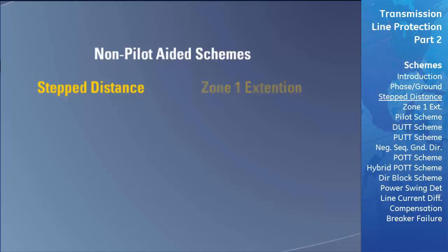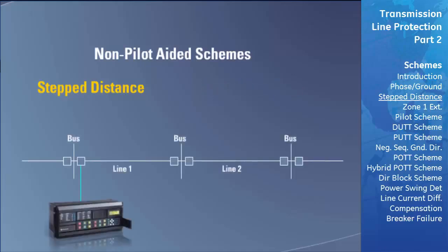We will first describe the stepped distance scheme, which is the basic structure for all other distance schemes. The stepped distance scheme uses four different zones of protection to protect its own transmission line and to act as a backup distance relay for adjacent lines. We will use the power system shown here to describe how the four zones are set and used. The main transmission line we will be protecting is transmission line number one, with the relay located at the far left of that line.